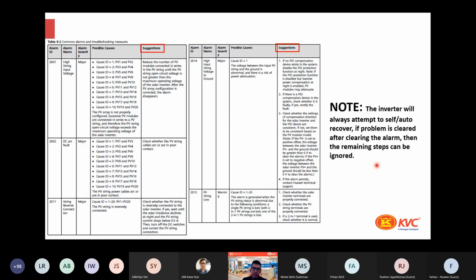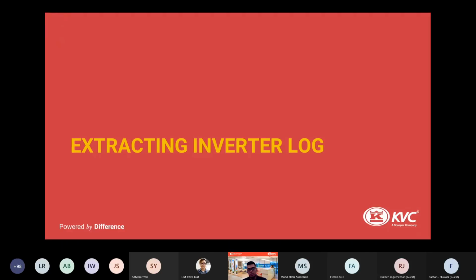So whenever you're able to clear the alarm on the Fusion Solar Management System or on the Sun2000 app, once you acknowledge the alarm and the inverter is already up and running, the remaining steps can be ignored. But if you try to clear the alarm and are unable to, and the recovery method still doesn't work, then we proceed to the next part, which is extracting the inverter log.